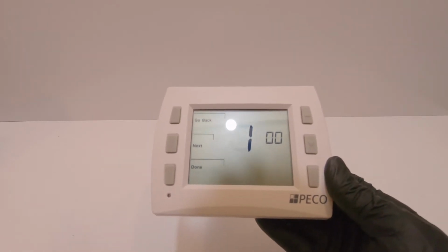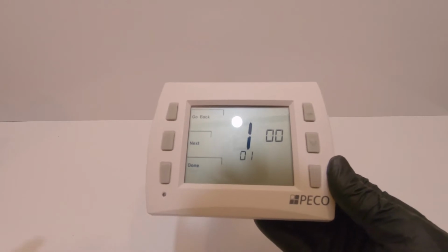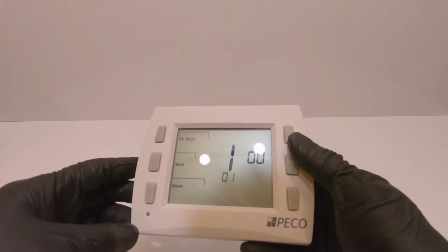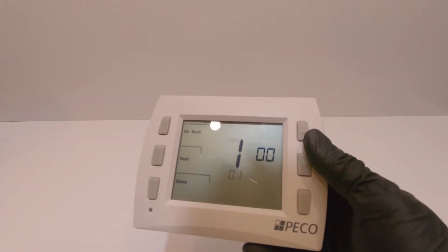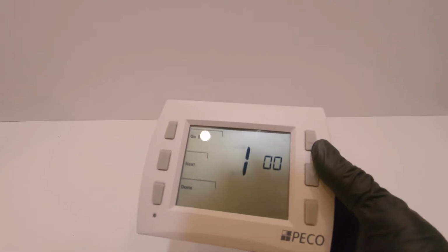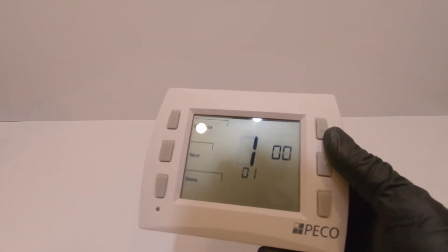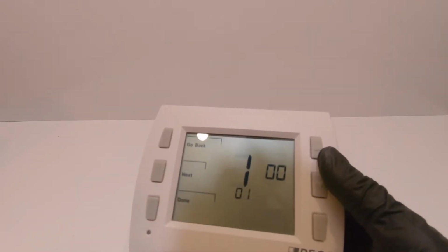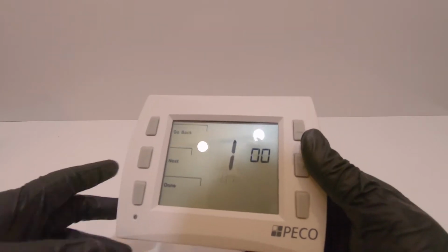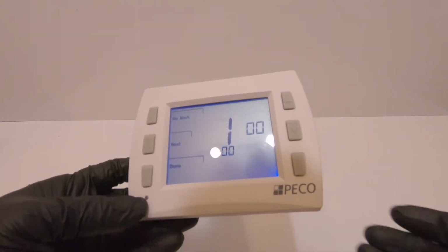Okay. Now, within the advanced settings, one of the things that we're going to have to make sure and make a decision on is how is this going to be set up as far as the schedule format. So you have a few settings here. You have 01. That particular setting is going to be to make the thermostat programmable, right? So you'll be able to go in, set your schedule, when you're going to turn it on and off, and temperatures and such. Now, you can also set this to 00, which is going to be a non-programmable.